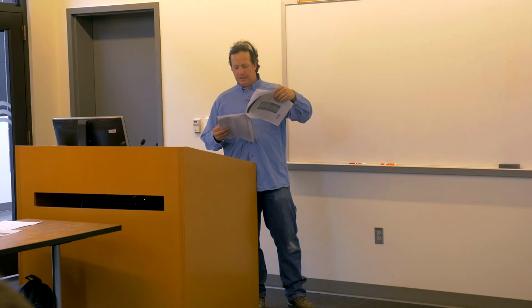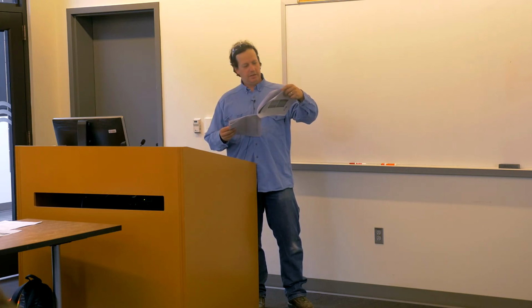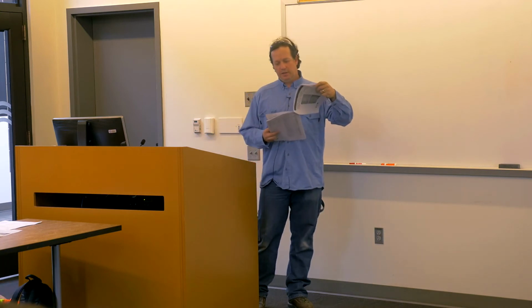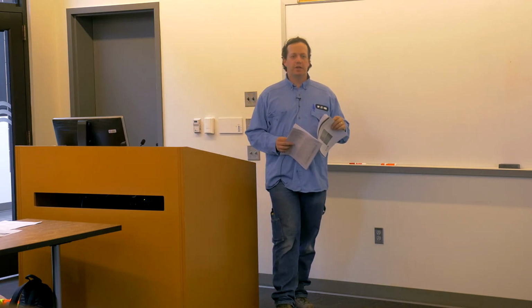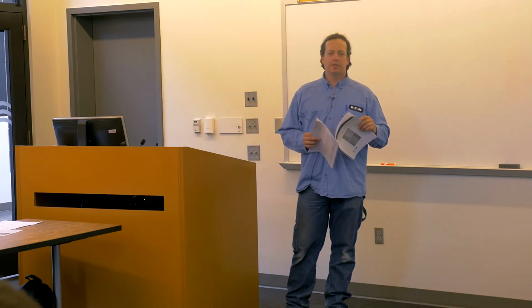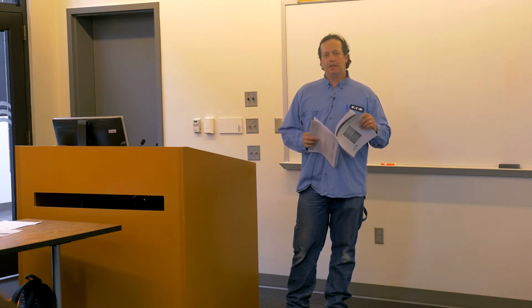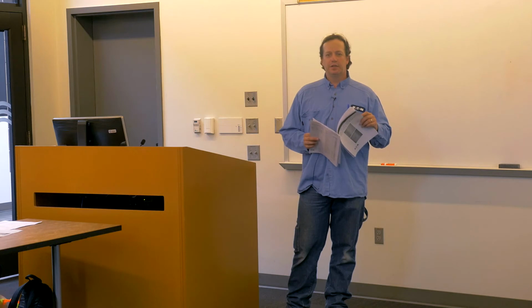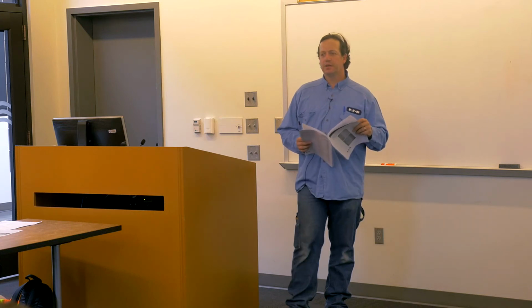That basically tells you an inspection schedule. I know, working at a NETA company, if you have high equipment failure, you increase your inspection rate until it's proven reliable. Typically, for a critical piece of equipment, they'll say check annually, and if you're having issues annually, you could bump it down to monthly if needed. But the goal is to get your maintenance window out to 3 to 5 years.